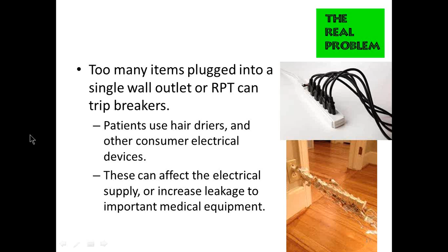CMS finally did give us a categorical waiver to allow for the use of power strips if you meet all these life safety code requirements. So the place to look is Life Safety Code 2012, the 2012 edition, for the power strip requirements. I'm going to summarize them here. It basically says you can use them to power cart-mounted, pedestal-mounted, table-mounted, or rack-mounted equipment if you meet all of these conditions below.